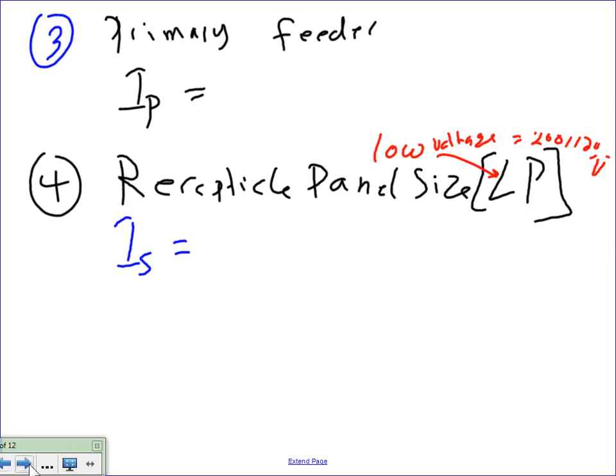Cool. Okay. Primary feeder. Now we're going to find the feeder that feeds that transformer, guys. Primary feeder. I want you to do the math for me. The primary feeder, I will take the 36.1. Remember that, guys, full load amps? The 36.1. Then I'm going to take the 36.1 and multiply. Now here's where you have to make a decision. If I want to take full advantage of my transformer and take the full 36.1 amps, then I have to multiply by 1.25 for continuous load.